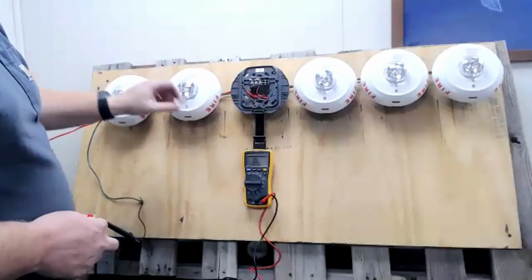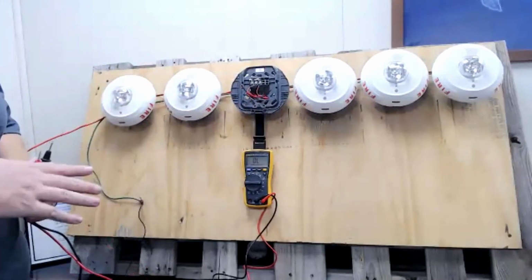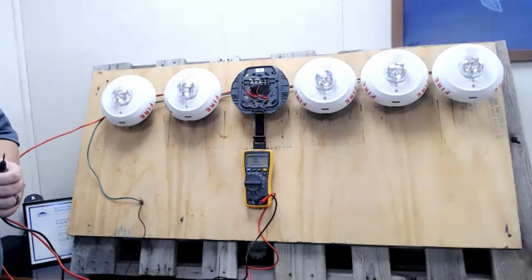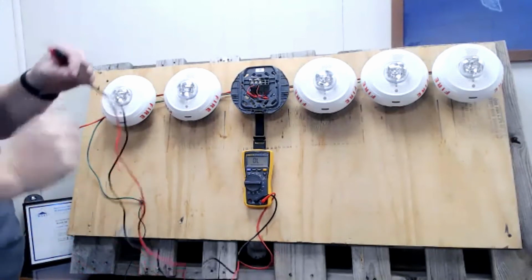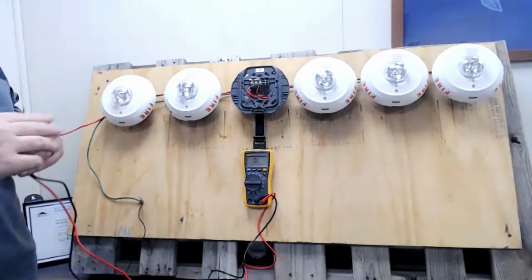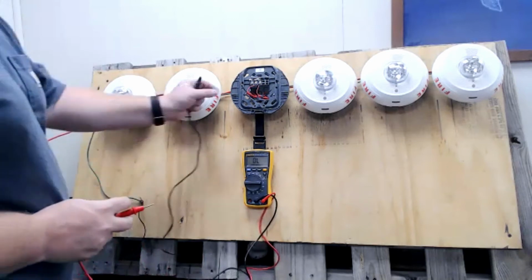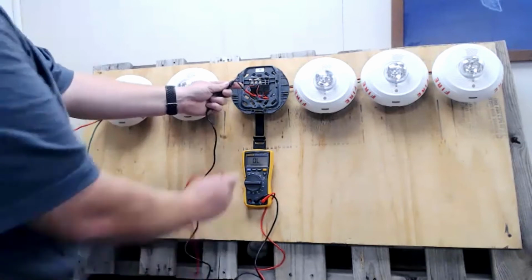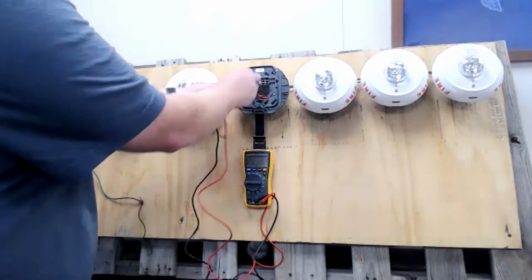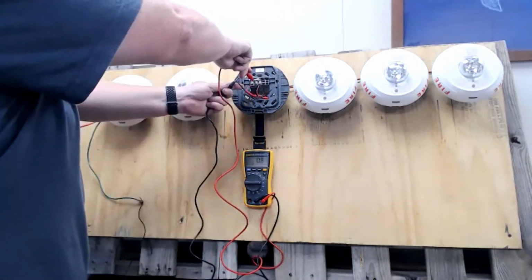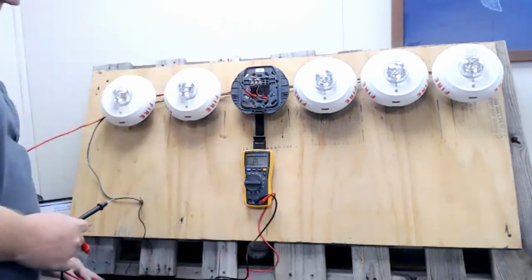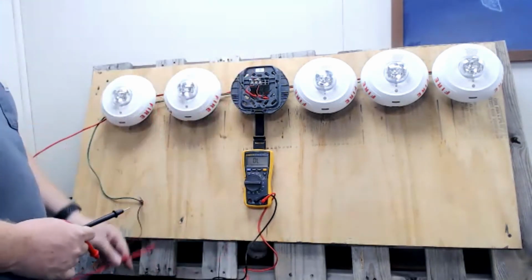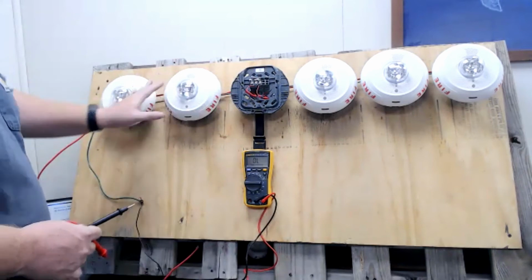Now, in this case, it's very easy to see that this wire goes this way and this wire goes that way. But if you've got your wires zip tied up real nice, they're going up into the ceiling, up to your bridle rings, you're going to have both of those side by side, and it can be hard to tell which one goes which way. So since I know it's on this one, I'm going to put my black meter lead here and my red meter lead here, just like I'm checking for resistance. And I see a hard short, which tells me it's on the side that my home run is on. So it's going to be one of these two devices.